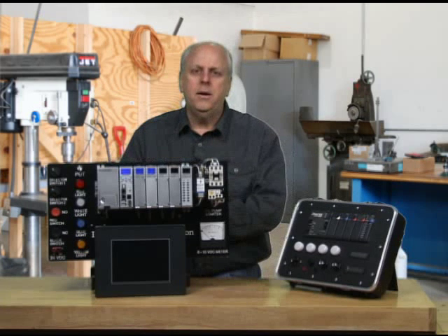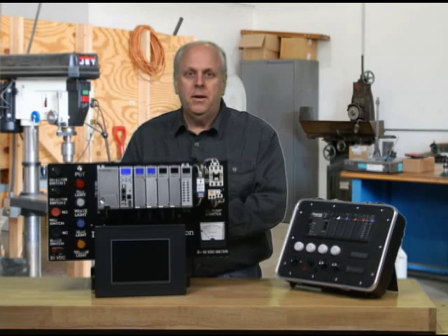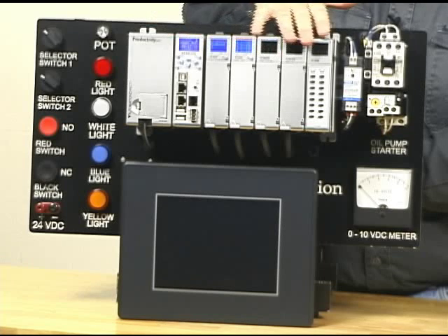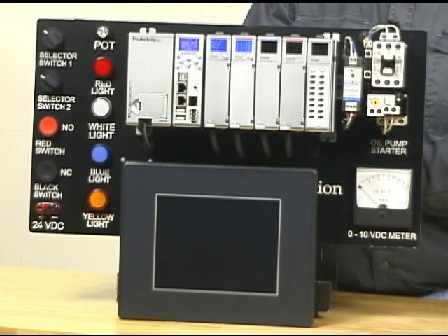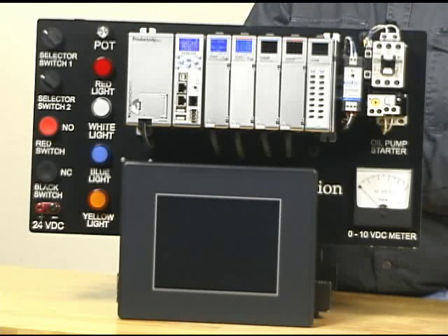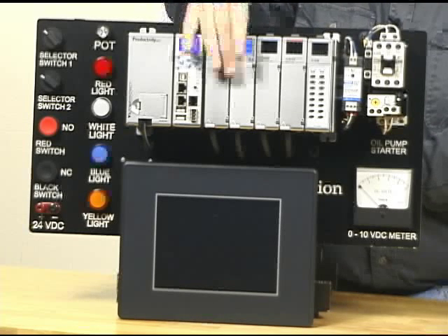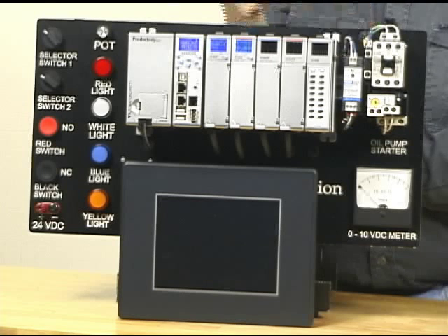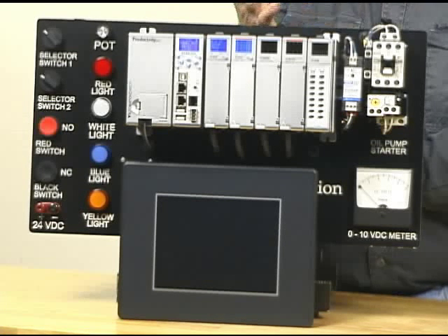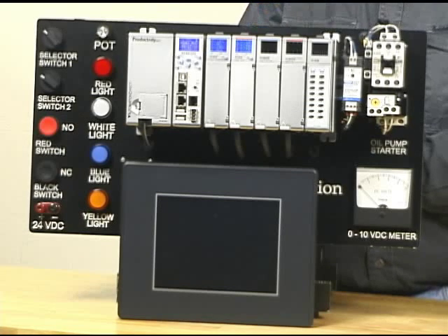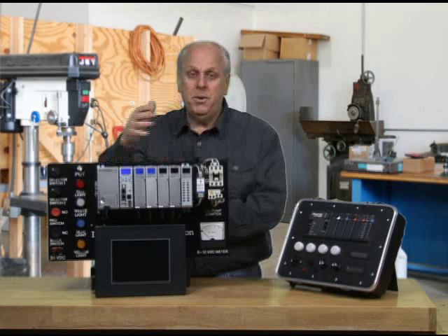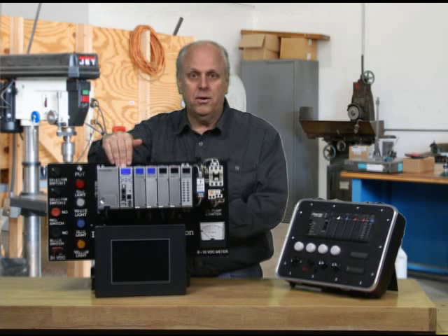This unit, there really is no addressing. What you do is when you go into the software, you're going to see the rack and such, and you're going to create what we call tag names. Names that mean something to you. Such as if I hook up a flow switch to an input on here, I'm going to give that input a name, flow switch. And when I write my program, I'm going to see those names in the program. I'm not going to see the physical address. So it's very user-friendly. Now, to make that work, we have to have the ability to download all your tag names into here, which it does.